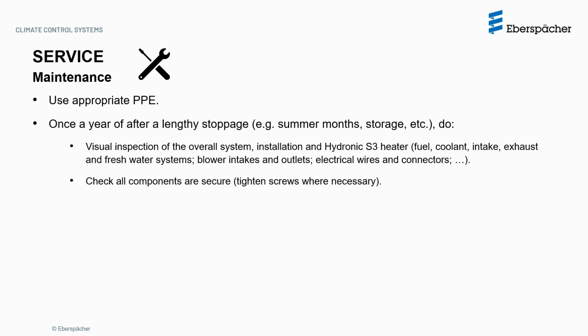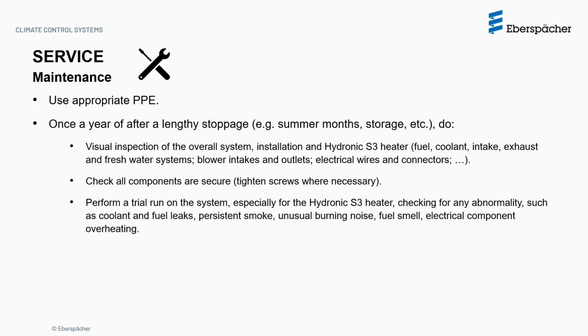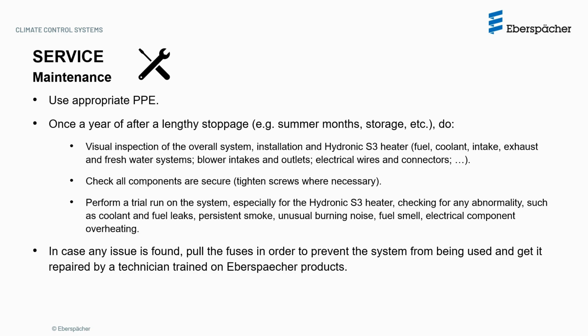Make sure all components are secure and tighten screws where necessary. Perform a trial run of the system, especially for the Hydronic S3 heater, checking for any abnormality, such as coolant and fuel leaks, persistent smoke, unusual burning noise, fuel smell, electrical components overheating. In case any issue is found, pull the fuses in order to prevent the system from being used and get it repaired by a technician trained on the Eberspächer products.